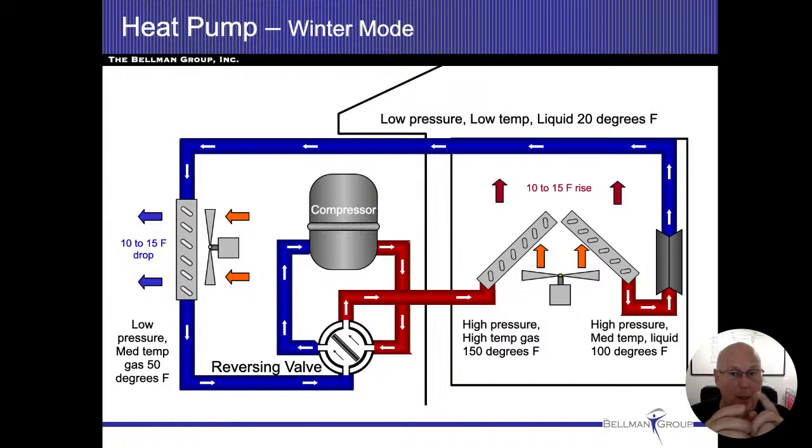So a heat pump, or I should say an air conditioning system, is technically a heat pump, all right? But when we use those terms, the difference between a heat pump and an air conditioning system is that reversing valve. In this diagram, you see it on the bottom there, and that changes the direction. So right now, this is in winter mode. So right now we're absorbing heat from the outside and we're bringing the heat to the inside of the house.